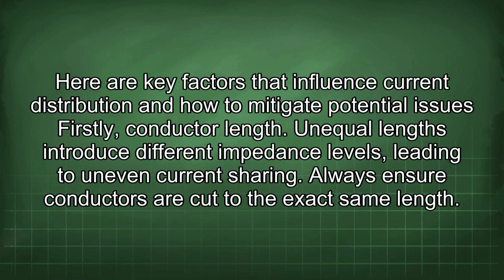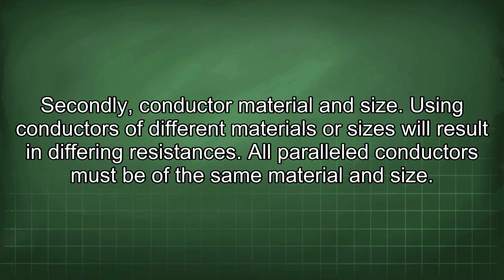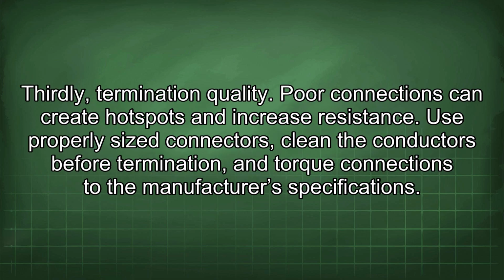Firstly, conductor length. Unequal lengths introduce different impedance levels, leading to uneven current sharing. Always ensure conductors are cut to the exact same length. Secondly, conductor material and size. Using conductors of different materials or sizes will result in differing resistances. All paralleled conductors must be of the same material and size. Thirdly, termination quality. Poor connections can create hotspots and increase resistance. Use properly sized connectors, clean the conductors before termination, and torque connections to the manufacturer's specifications.